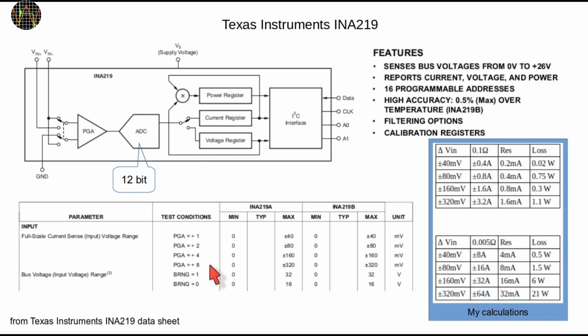To show what that means, I added these 2 tables. The top one is for a shunt of 0.1 ohm and the lower one is for 0.005 or 5 milliohms. As you can see, with a 0.1 ohm shunt, the range goes from sub-milliamps all the way to 3.2 amps. For the 5 milliohm shunt, you can measure up to 64 amps plus minus with a resolution of 32 milliamps. The loss column is the needed power rating for the shunt resistor.